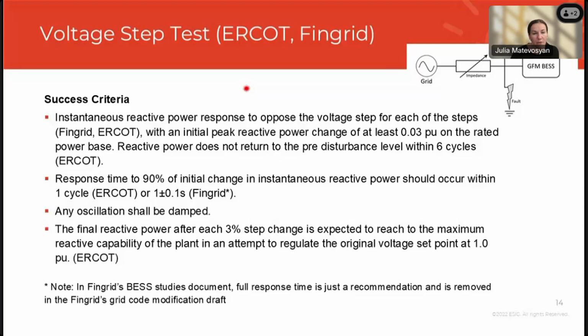with initial peak reactive current change to at least 0.03 per unit of rated as defined by ERCOT. And ERCOT also defines that reactive power should not return to pre-disturbance level within at least 6 cycles. Response time to 90% is defined by ERCOT and FinGrid. Kind of there is a pretty big difference here. 1 cycle for ERCOT, 1 second for FinGrid. Again, for FinGrid, this is recommended value.